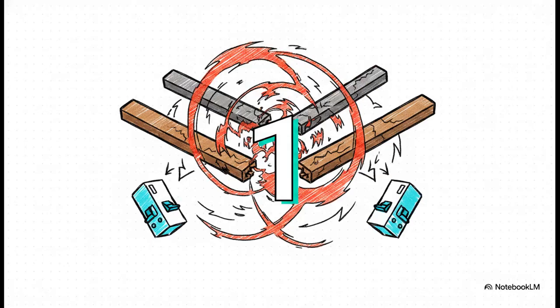And that brings us to a terrifyingly brief window: 1 single second. That is the standard short-circuit duration. It tells you exactly how long your switchboard has to physically survive the extreme thermal and mechanical violence of a fault before the circuit breakers can manage to clear it. Now, 1 second might sound fast, but in electrical terms, an arc fault raging for 1 full second is an absolute eternity for copper and steel to endure.